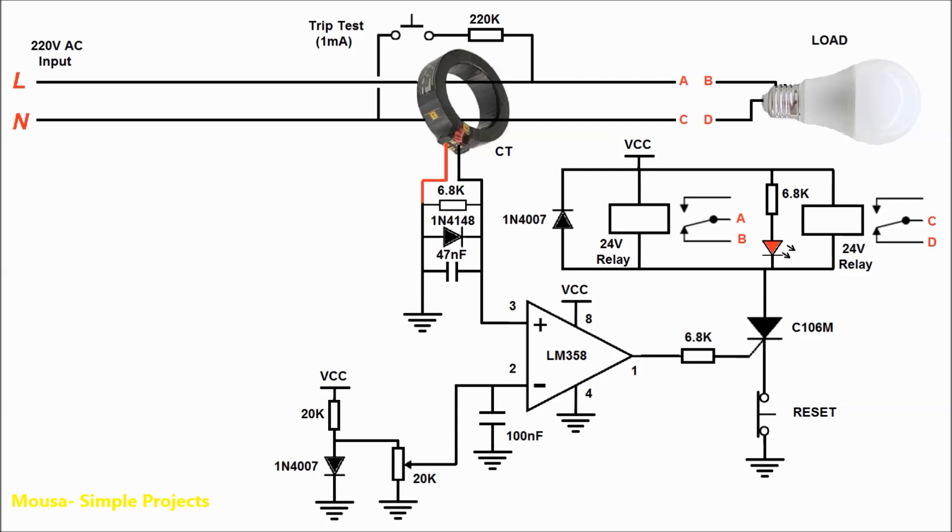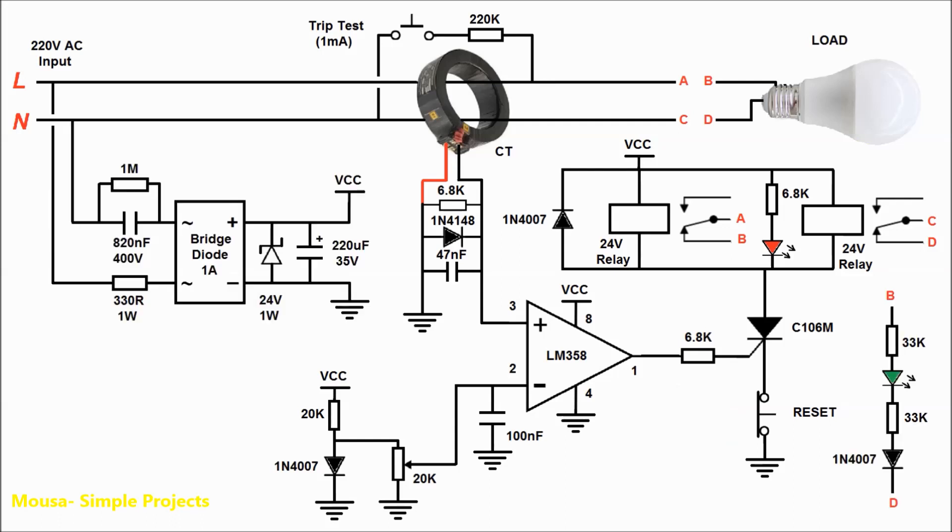And finally, the last part is a power supply that converts 220-volt AC voltage to 24-volt DC voltage. By pushing this test push button, we're making one milliamp unbalanced current to see if the circuit is working well or not. This LED is an indicator to show you that the mains voltage is connected to the load.